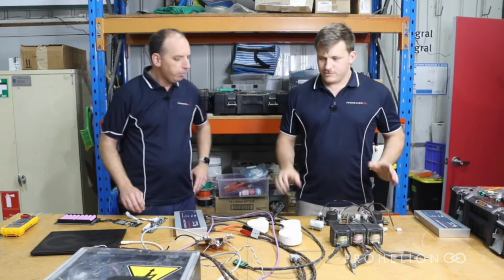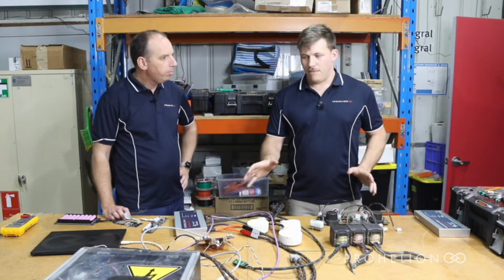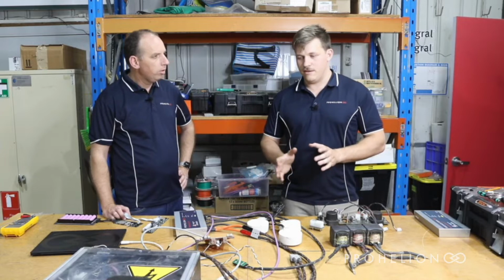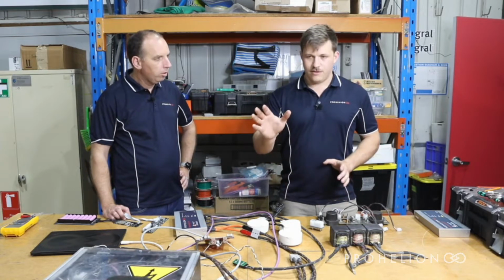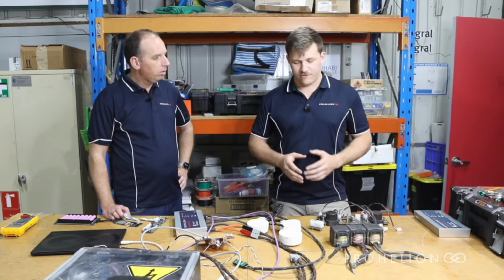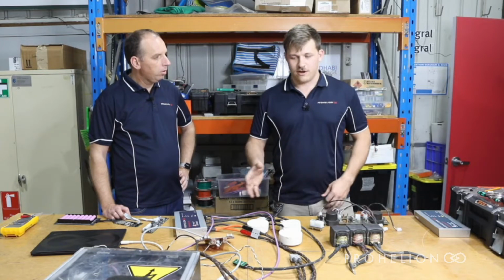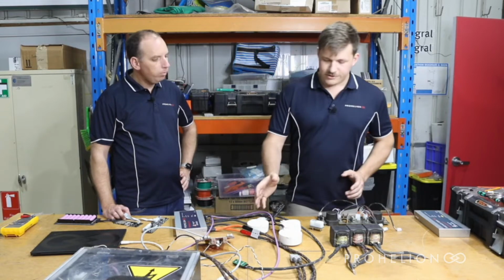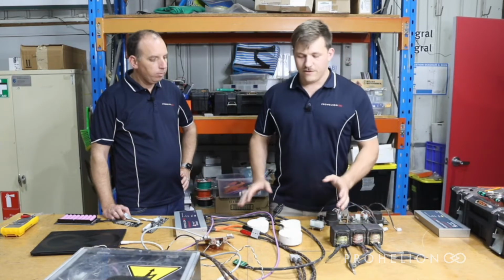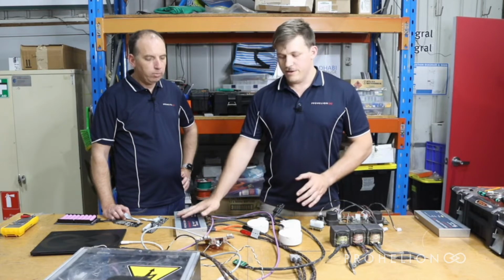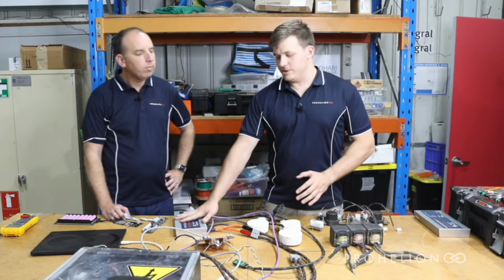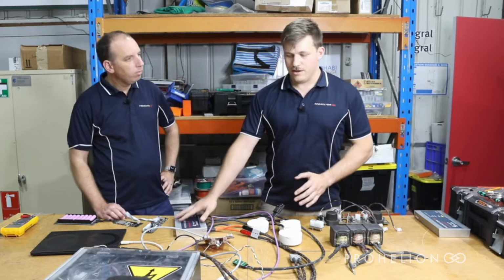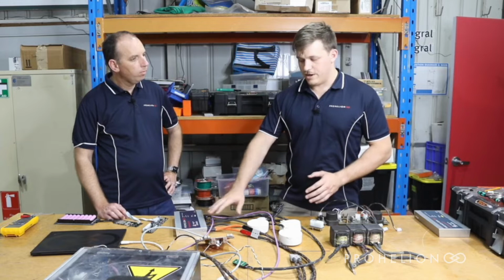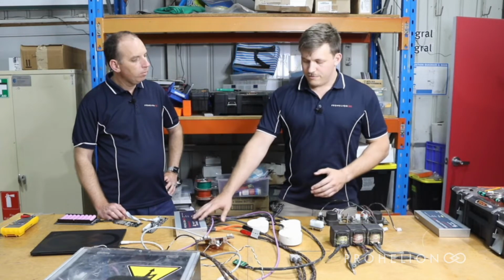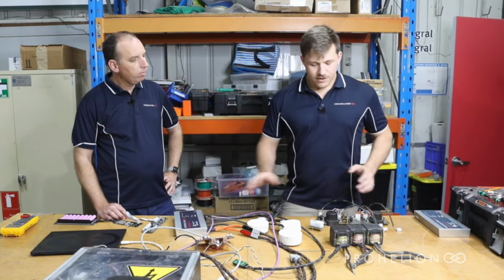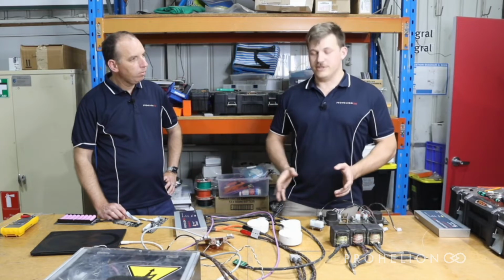Yeah, sure. So on these high-powered or even small capacity battery systems, the batteries themselves have a really low impedance in terms of being a source, and they can discharge a lot of current very quickly. When you go to connect a battery to an inverter, most inverters will have a large DC capacitor bank that is used for filtering and stabilizing input DC for the motor controller itself. That can cause, or will cause, a very large inrush of current.